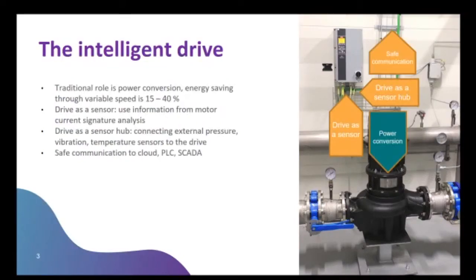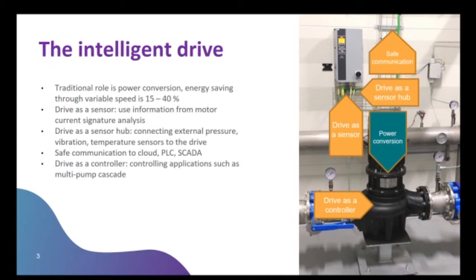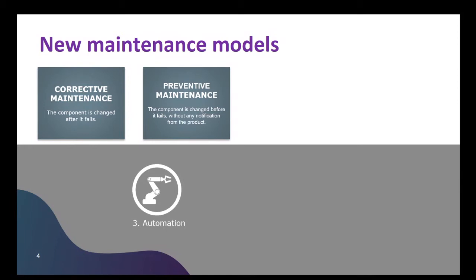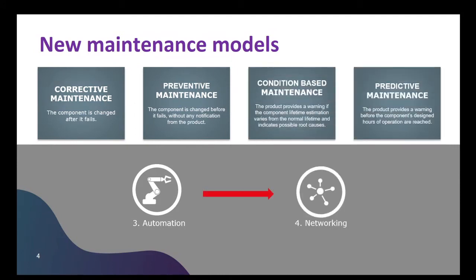Okay. Then the drive can also be used as a controller for controlling the application. In case of water application, it can be multi-pump cascade application where we have multiple pumps staged in and out depending on the demand. So all this intelligence now comes into the drive, and this enables us to move from corrective maintenance, where we were repairing components which were broken, to a more predictive maintenance or condition-based maintenance, where we see ahead what happens. And this is enabled by the availability of the data sensed by the drive.